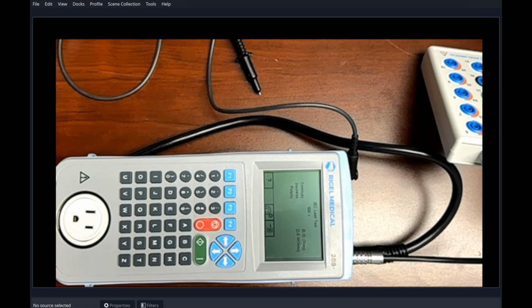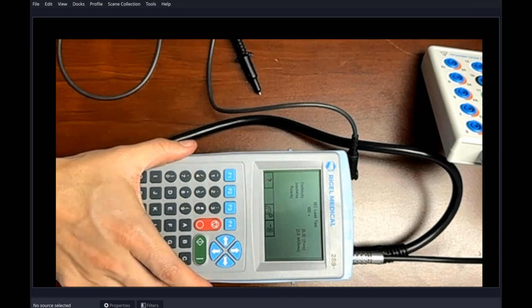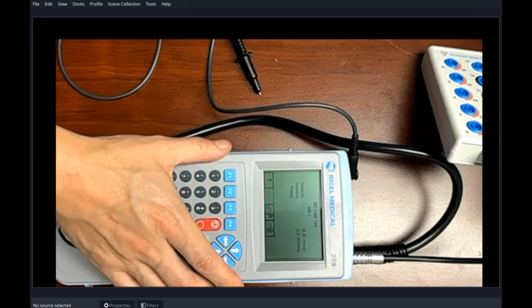The safe test range is a little bit different. That's 90 to 264 volts, and that covers both frequencies. So the types of voltage is covered across both ranges, whereas this is two different types of testers. You've either got a 120 volt or you've got a 230.